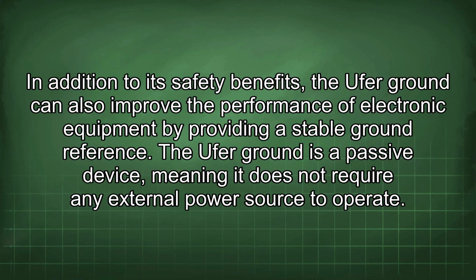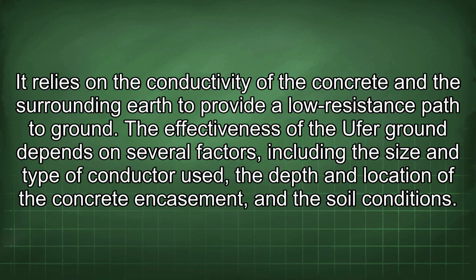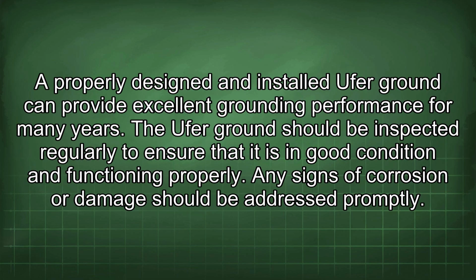The Ufer ground is a passive device, meaning it does not require any external power source to operate. It relies on the conductivity of the concrete and the surrounding earth to provide a low-resistance path to ground. The effectiveness of the Ufer ground depends on several factors, including the size and type of conductor used, the depth and location of the concrete encasement, and the soil conditions. A properly designed and installed Ufer ground can provide excellent grounding performance for many years.